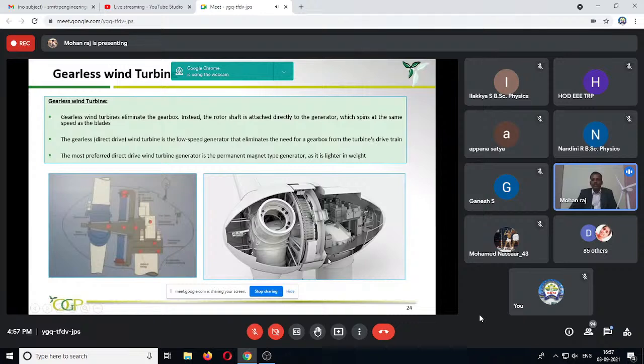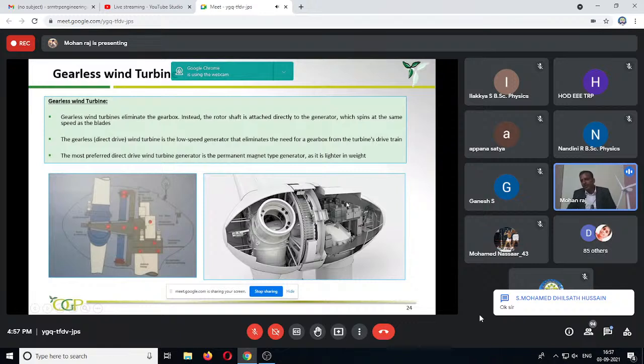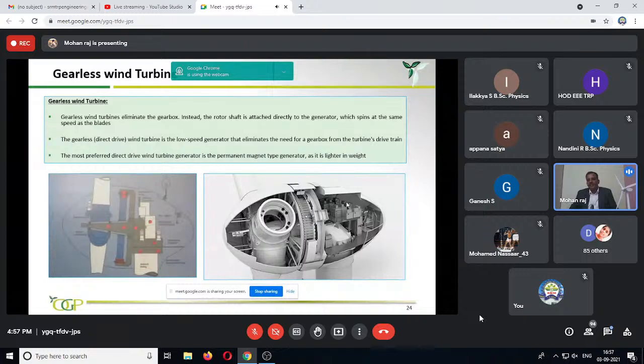Further, it is connected to the transformer through cable, and there is a lot of electronic equipment available for controlling the wind turbine, for controlling the braking. One, as I said, is the pitching operation, which does the aerodynamic braking, and the other is the mechanical braking. Normally, the mechanical braking uses hydraulic motors. You see, a lot of cars and two-wheelers use disc brakes. So the hydraulic pressure will be applied to the braking shoes. Automatically, the turbine will go off. For that purpose, there are a lot of electronic controllers available in the nacelle.